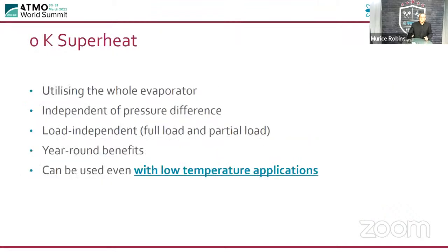So zero K superheat, as I said, we're utilizing the whole evaporator, and it's independent of pressure difference. So this doesn't make a difference at all. Decreasing the superheat and using the full evaporator works on all loads as well. It doesn't matter whether it's a full load or a low load. In other words, day or night. It doesn't matter if it's summer. It doesn't matter if it's winter. The benefits are year round, and there's no influence from ambient conditions. The system is basically working flat out day and night, 365, 7 days a week.